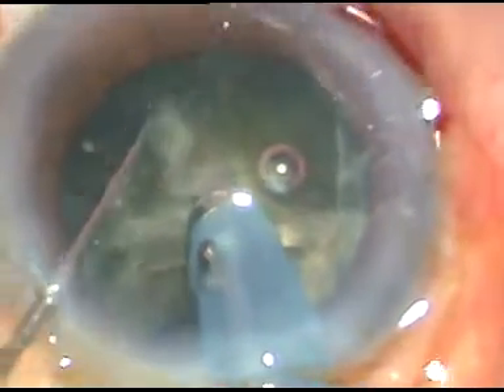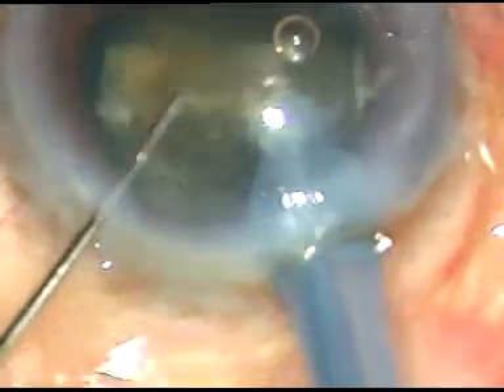Heminucleus. Now each heminucleus is being chopped into two parts. This is one heminucleus, and this free fragment is being emulsified. Now this is the other heminucleus, and it is being chopped, and at this time the machine is now in Phaco 2 mode, where the phaco power is about 70%, flow rate is 45 ml per minute, and vacuum is 450 millimeter of mercury. These settings differ from machine to machine.